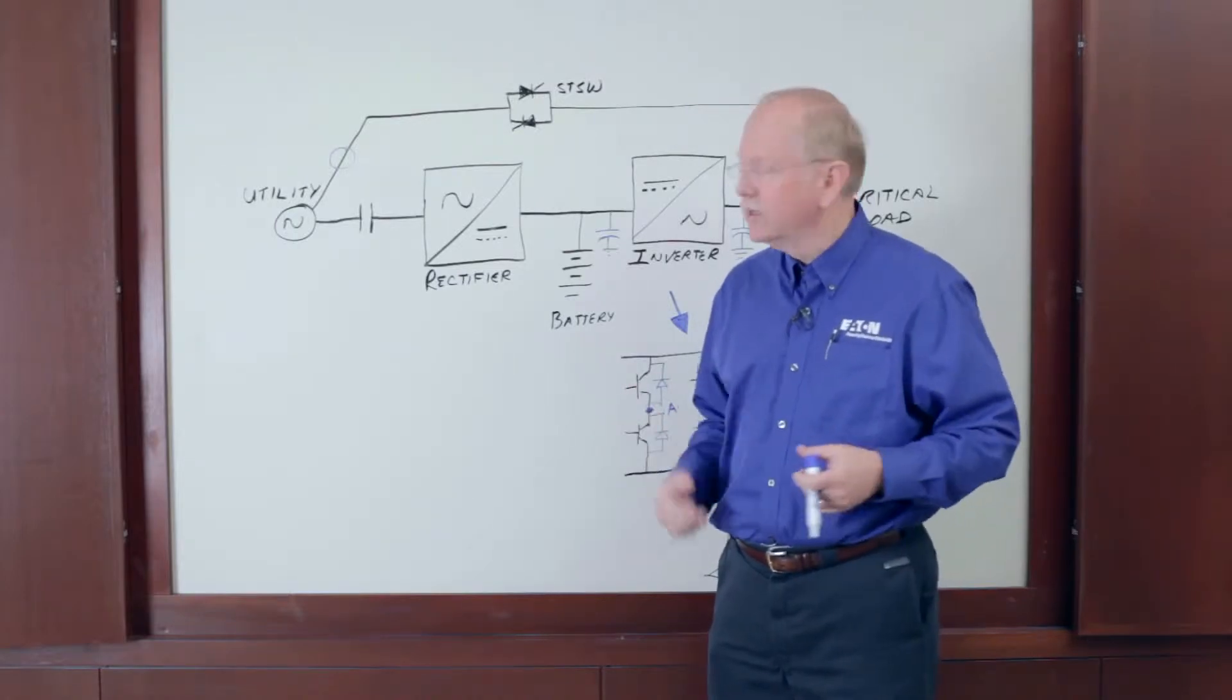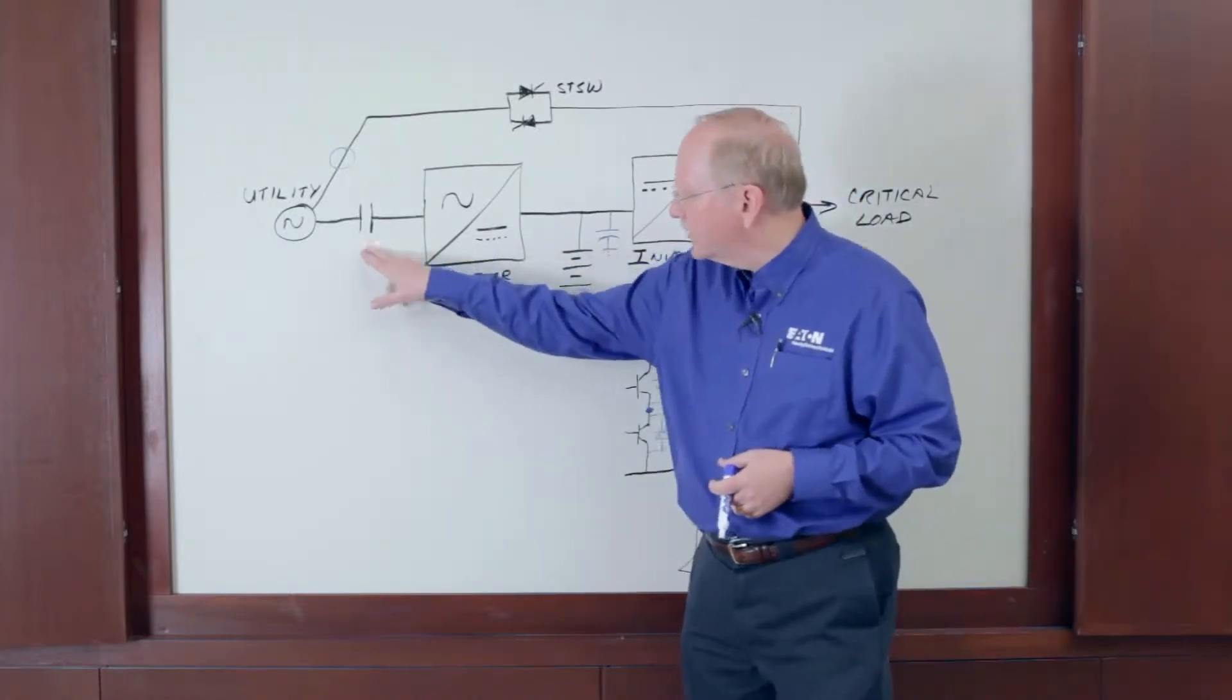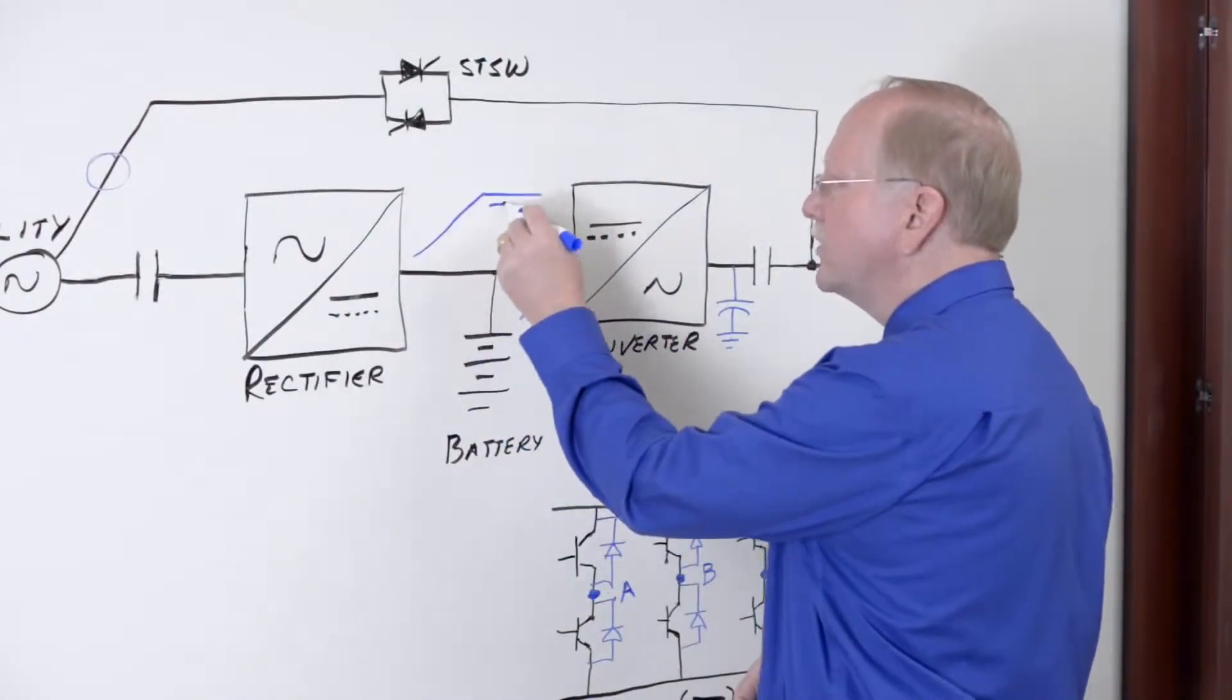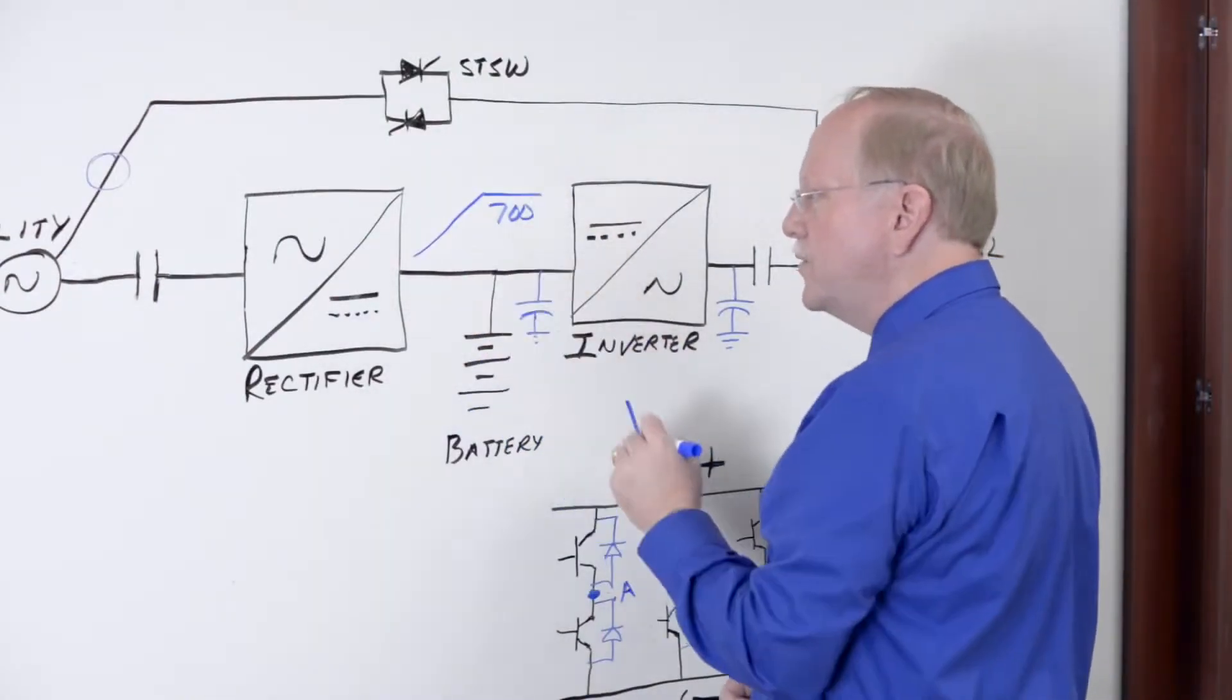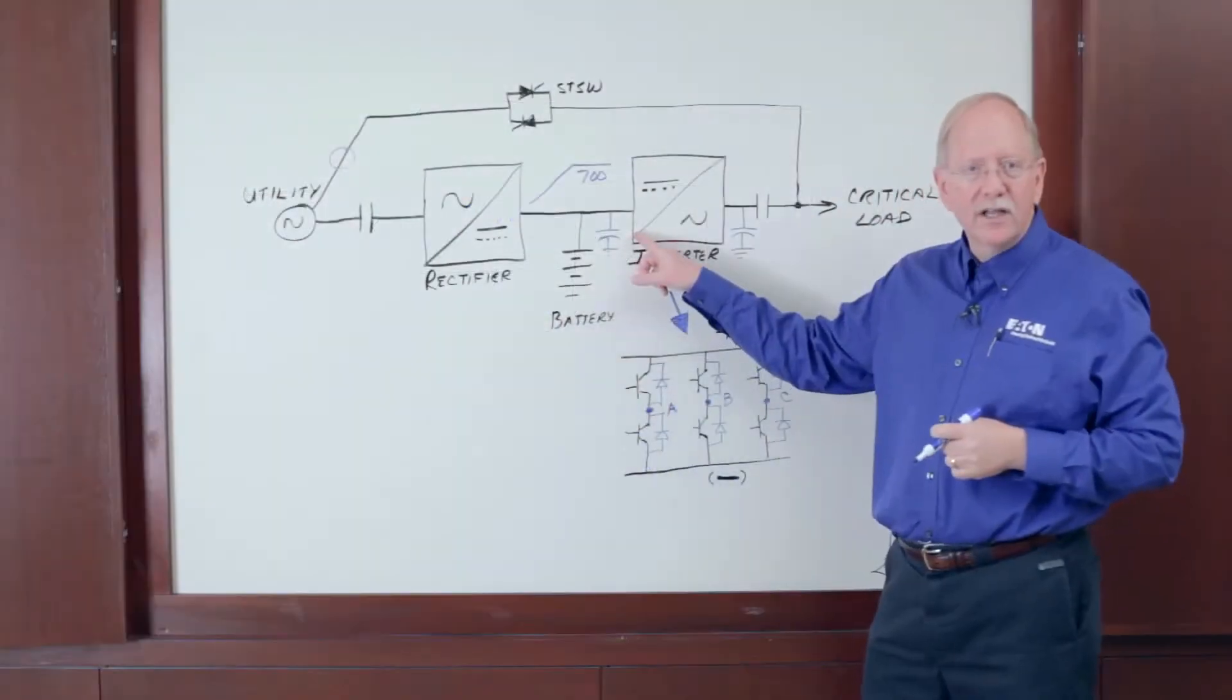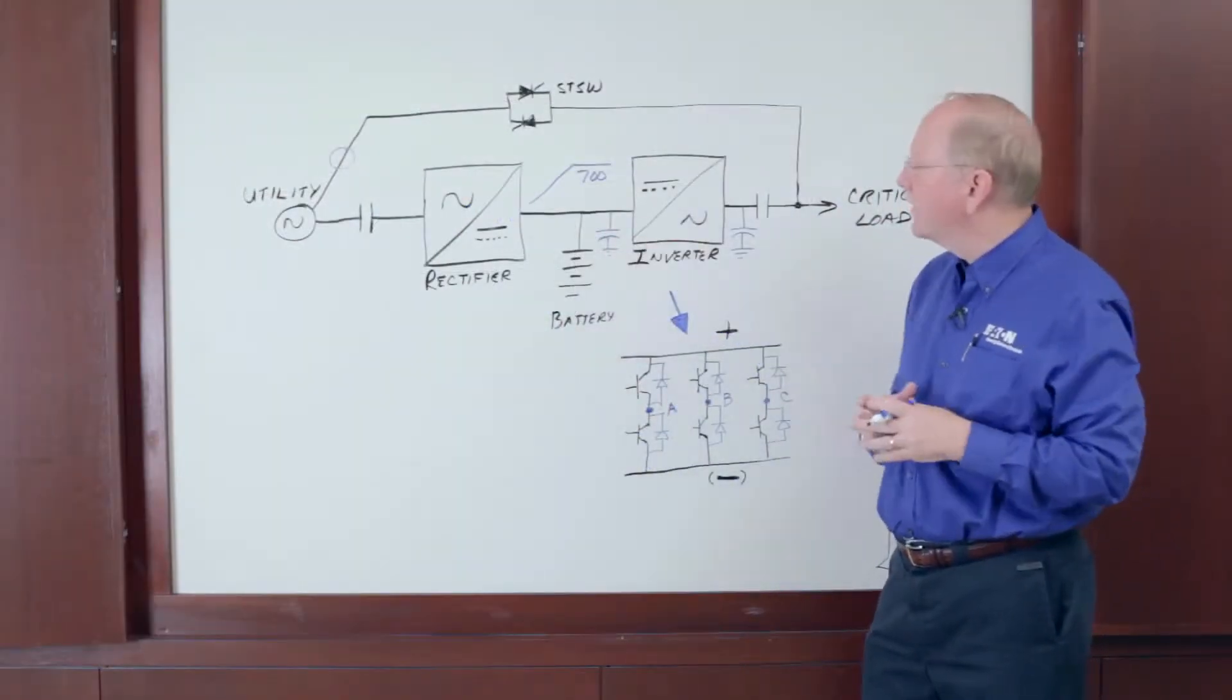How do we do that traditionally? Well, you've got to close the input contactor. You have to wait for the rectifier to ramp from zero to 700 volts DC. It's got to do that slowly over about 30 seconds or else you'll stress the capacitors connected in the DC link between the rectifier and the inverter.